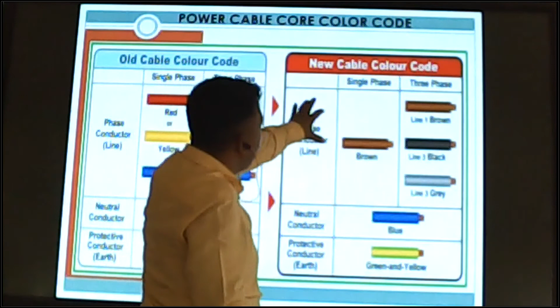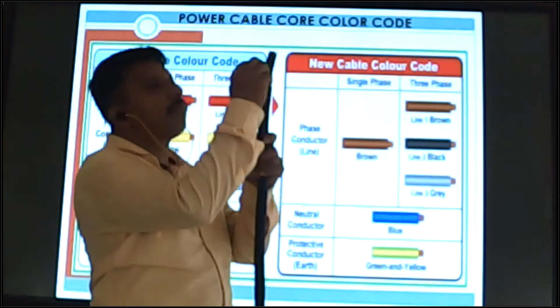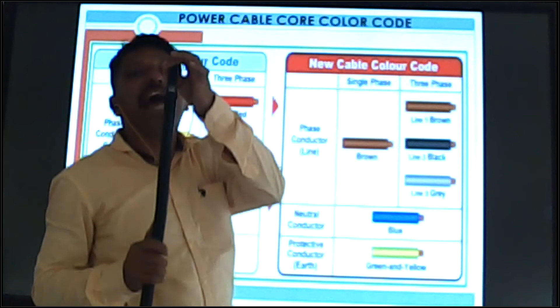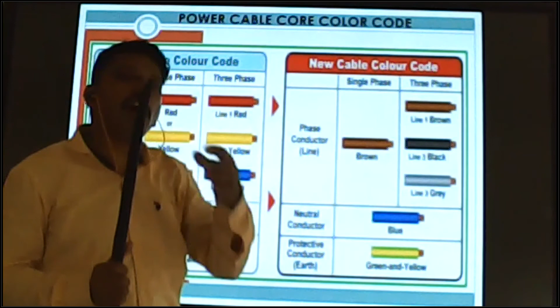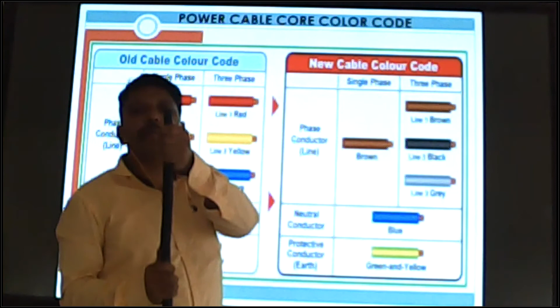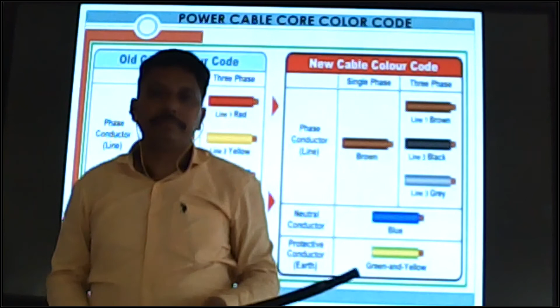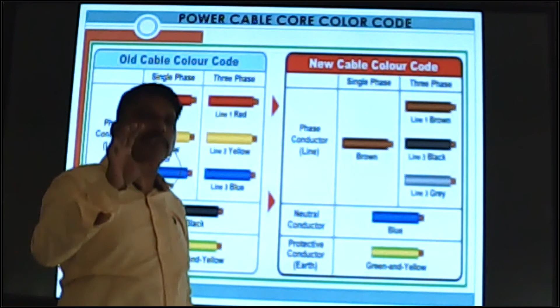Okay, so we can check the color code and termination. First, do not get confused about this one, new color code and old color code. First, if you are going to terminate a cable, first remove the insulation of the cable and check the inside core color code. Which type of color code is inside the core? As per this, you can do the termination. If the old color code core is inside, you can follow the old color code. If the new color code cable core is inside, you can follow the new color code termination. Okay, so at termination time, first check the cable's inside core color code.